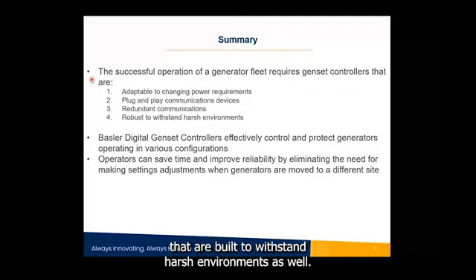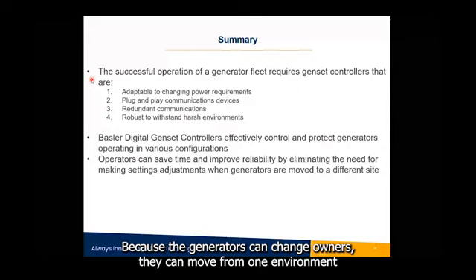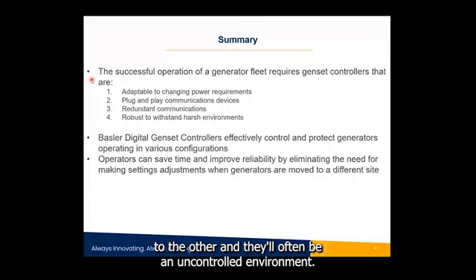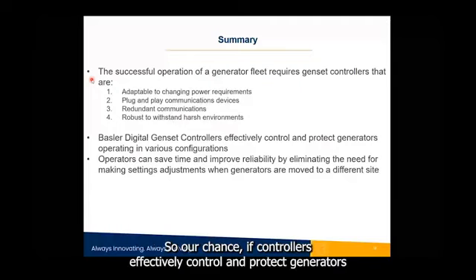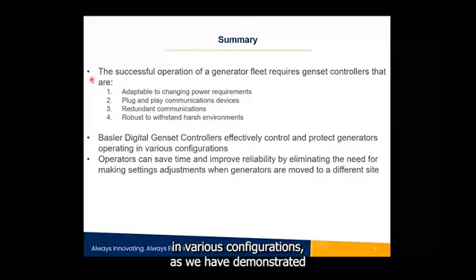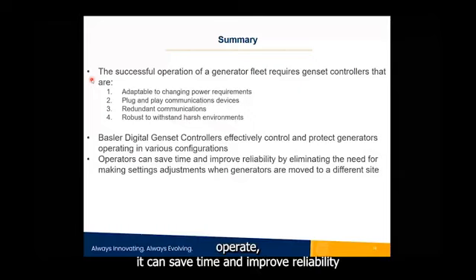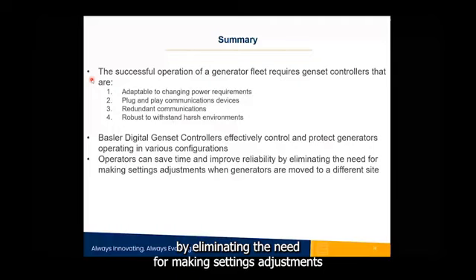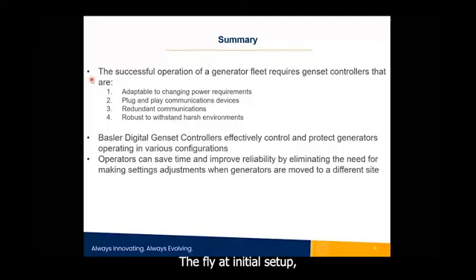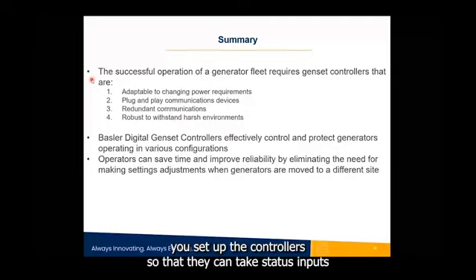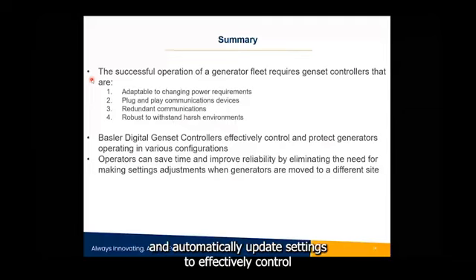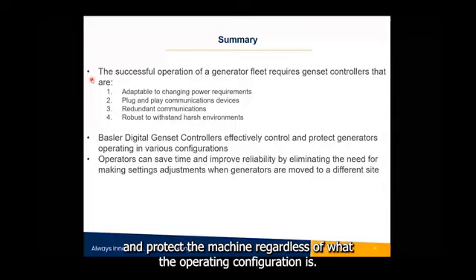And controllers that are built to withstand harsh environments as well, because the generators can change owners, they can move from one environment to the other, and they'll often be in uncontrolled environments. So our genset controllers effectively control and protect generators in various configurations, as we have demonstrated. And operators can save time and improve reliability by eliminating the need for making settings adjustments when generators are moved to a different site. This is done on the fly at initial setup. You set up the controllers so that they can take status inputs and automatically update settings to effectively control and protect the machine regardless of what the operating configuration is.